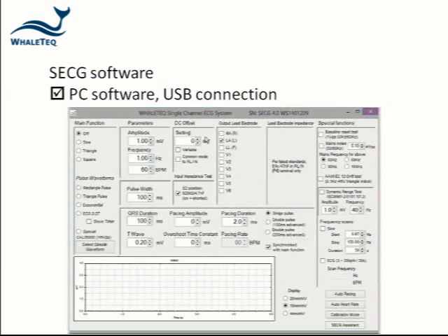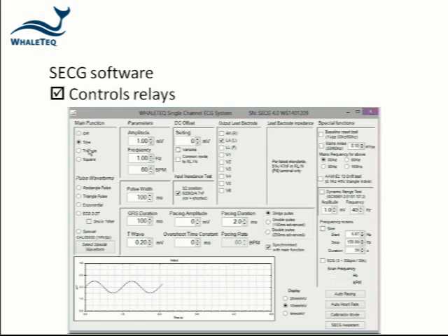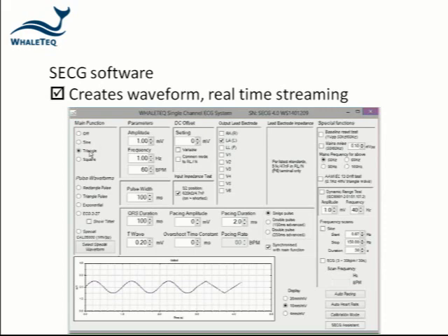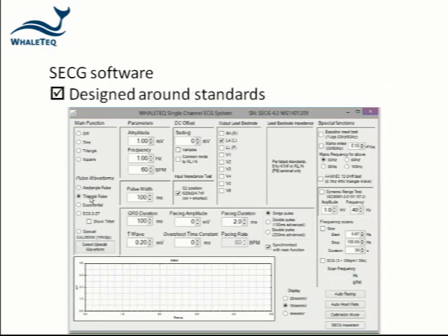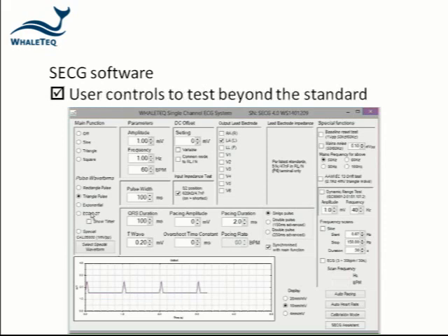The hardware is controlled by PC software via a USB connection. The PC software controls the relays and creates the waveforms using real-time streaming, allowing greater flexibility and resolution than a firmware solution. Although designed around IEC and AAMI standards, the user has access to controls that allow testing well beyond the limits in the standard.